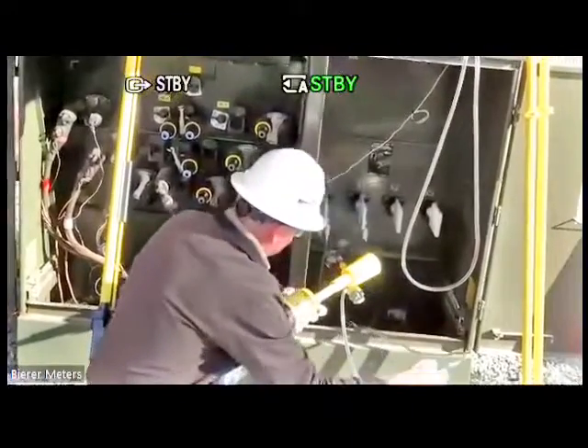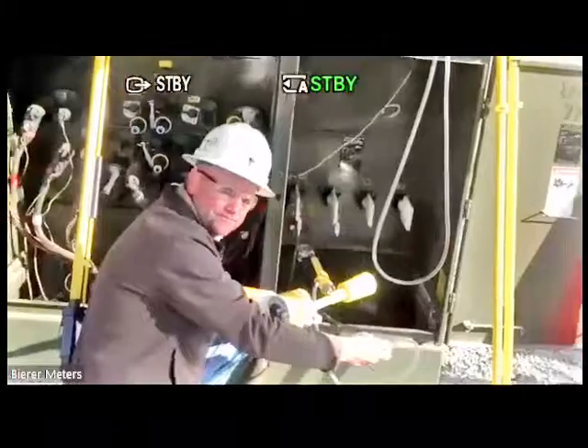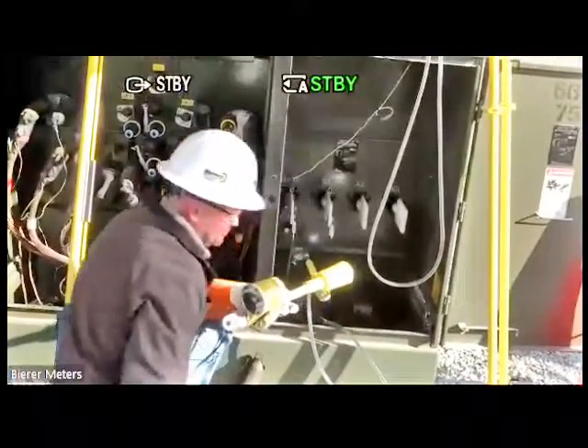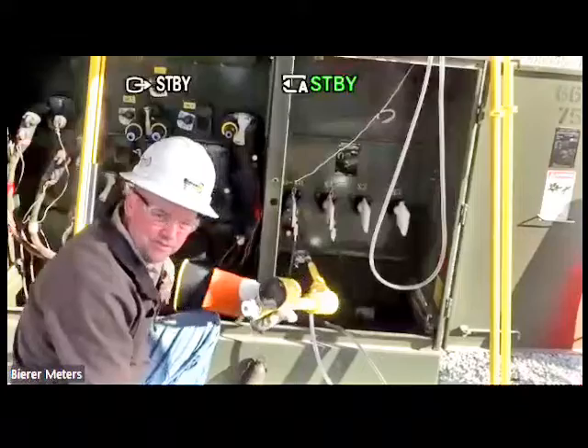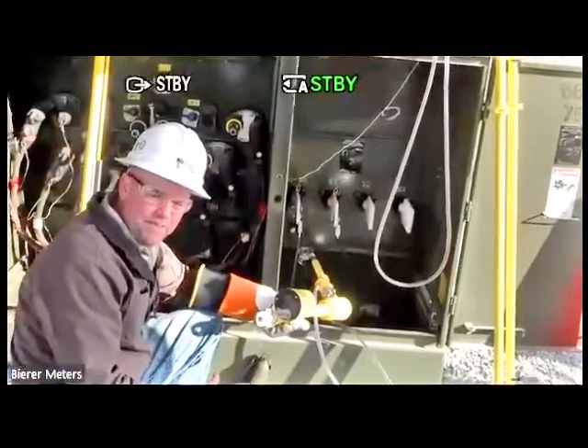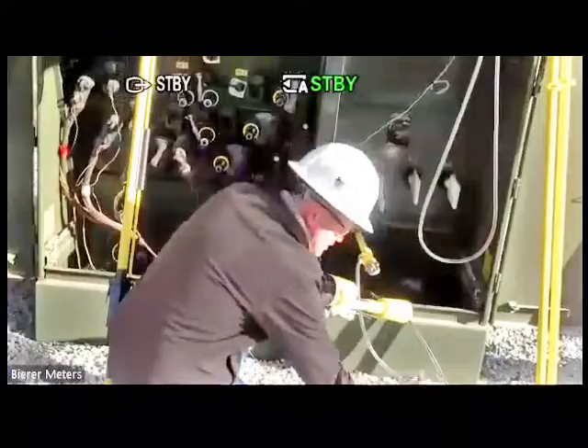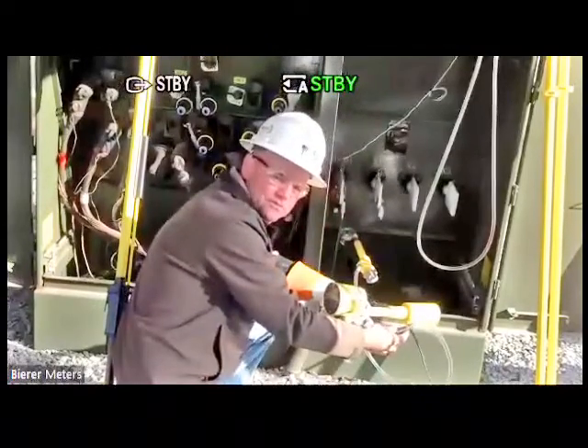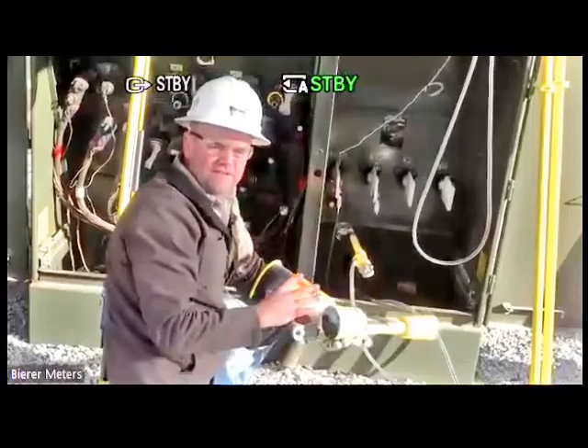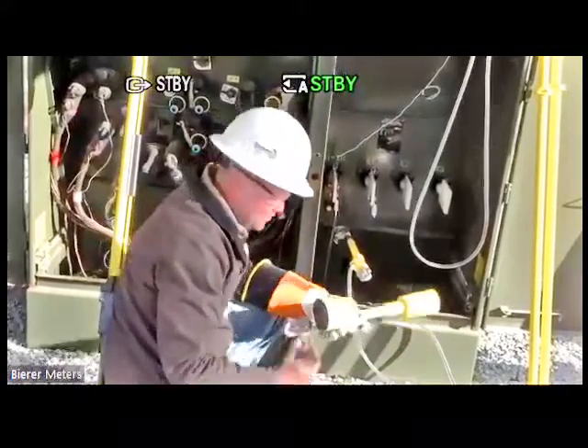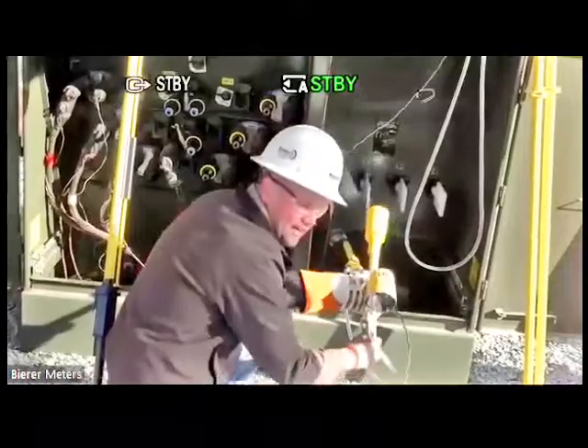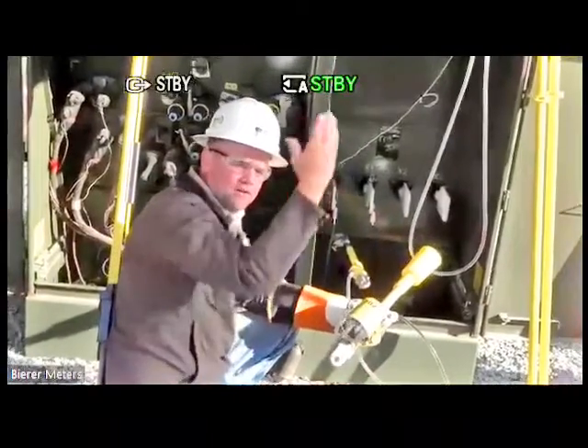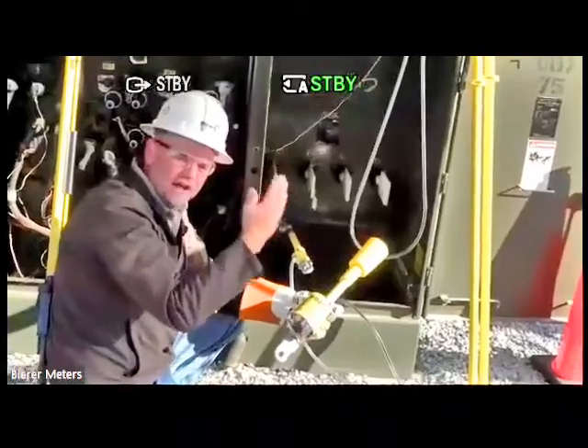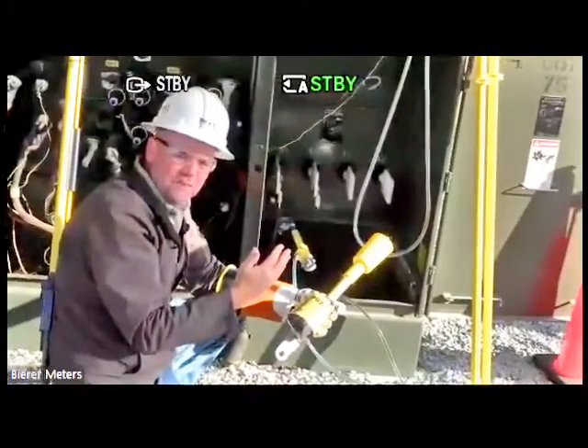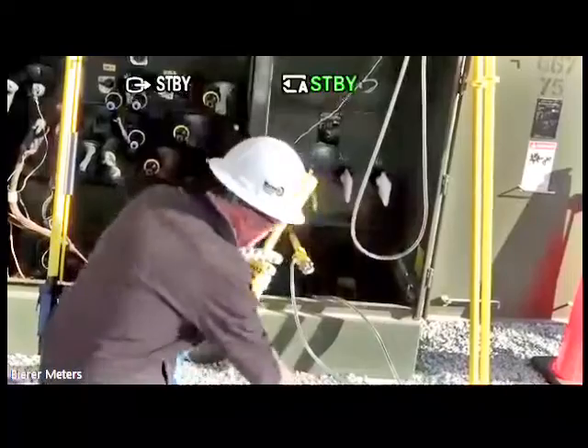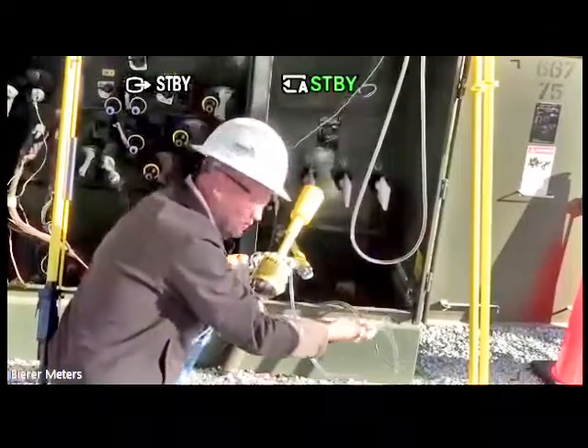Or you can use this, which is just an alligator clip. Now, as I mentioned earlier, if you go with just an alligator clip to ground like this, you have to keep in mind that you have a ground potential right here at this cable. So if you're doing this in an overhead situation, what you can run into is if I have a ground right here and I'm working from a stick and I overshoot and go to the conductor, you have that ground potential. That's not a very safe method, obviously, right? Because I have no protection in this circuit, no second probe.